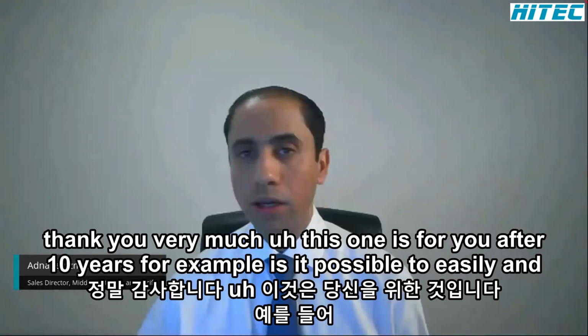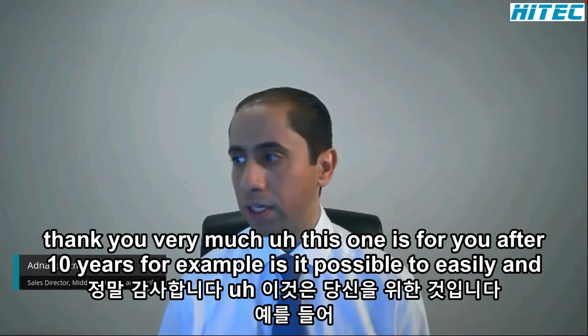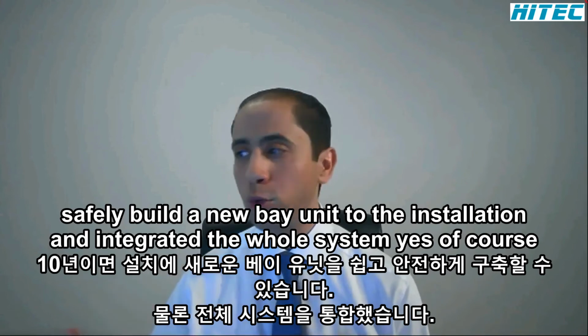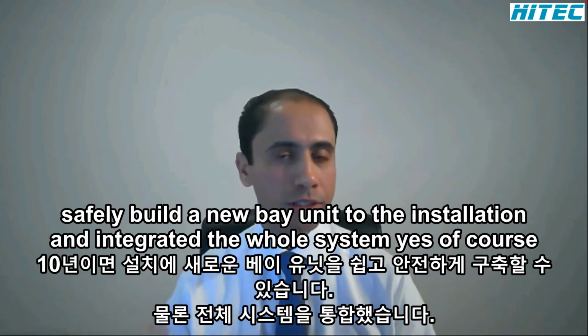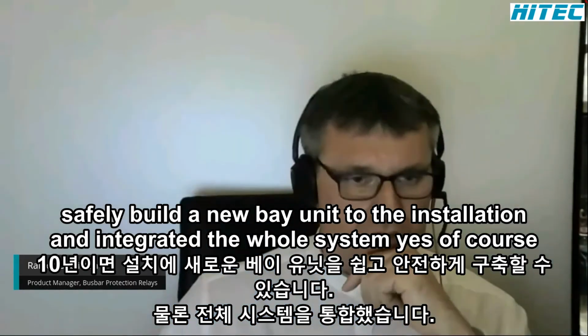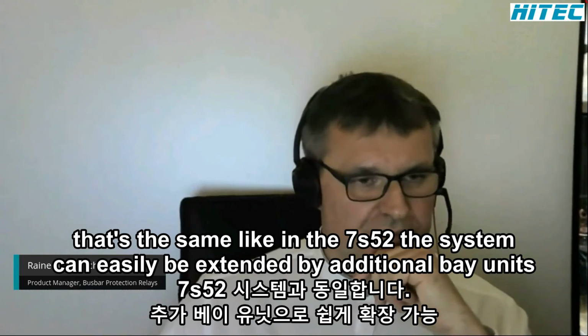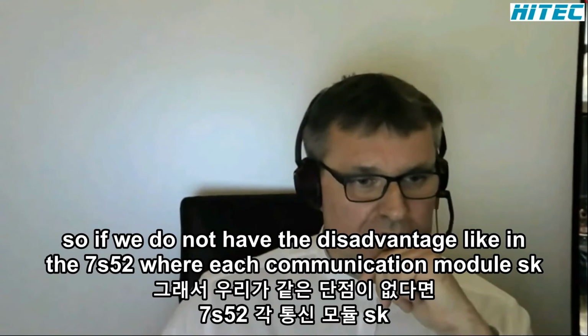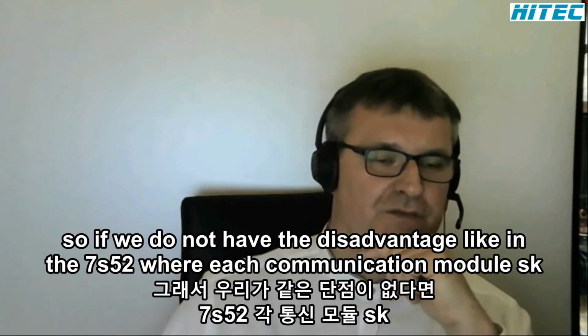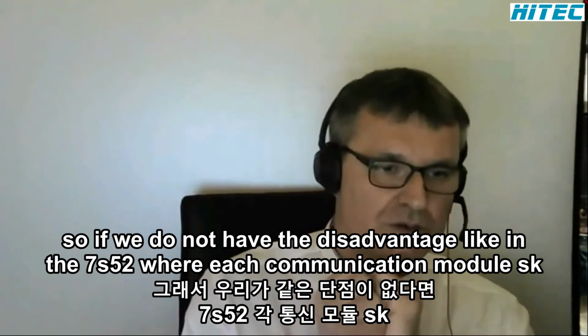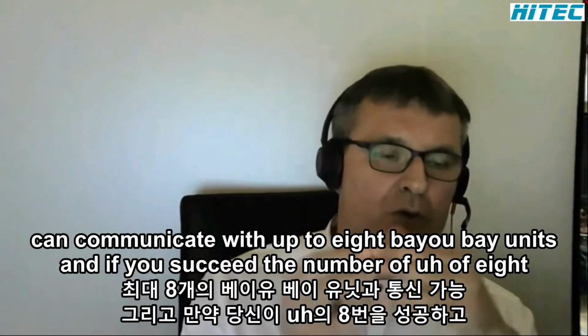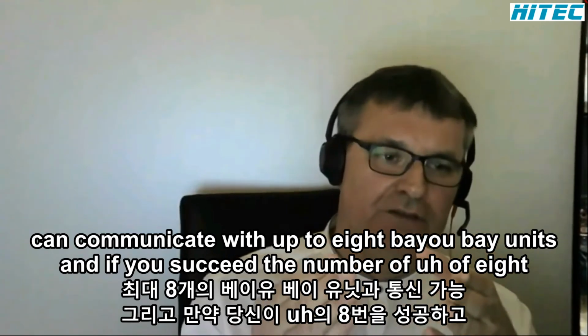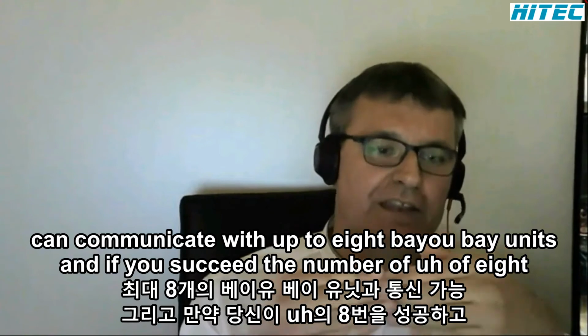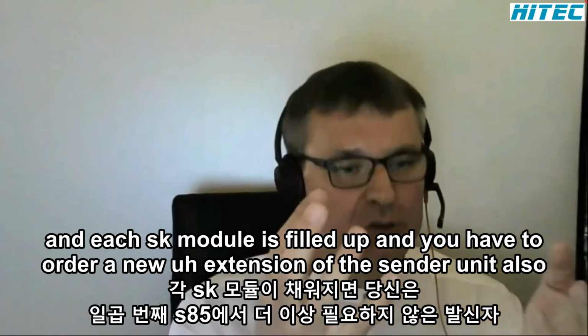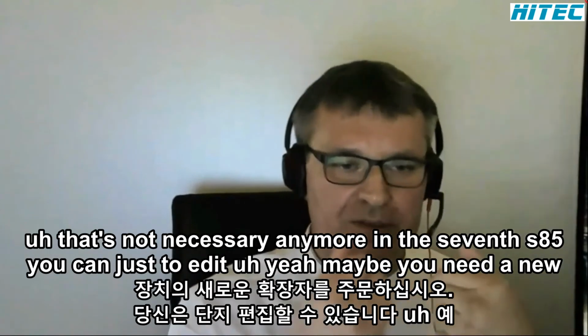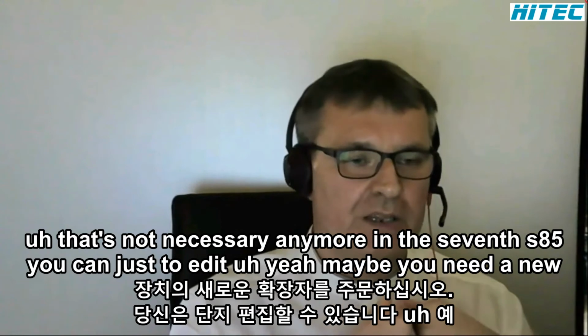Thank you very much. Rainer, this one is for you. After 10 years, for example, is it possible to easily and safely add a new bay unit to the installation and integrate it into the whole system? Yes, of course. That's the same as in the 7SS52. The system can easily be extended by additional bay units. We do not have the disadvantage like in the 7SS52, where each communication module SK can communicate with up to 8 bay units, and if you exceed the number of 8 and each SK module is filled up, you have to order a new extension of the sender unit also. That's not necessary anymore in the 7SS85. You can just add it.